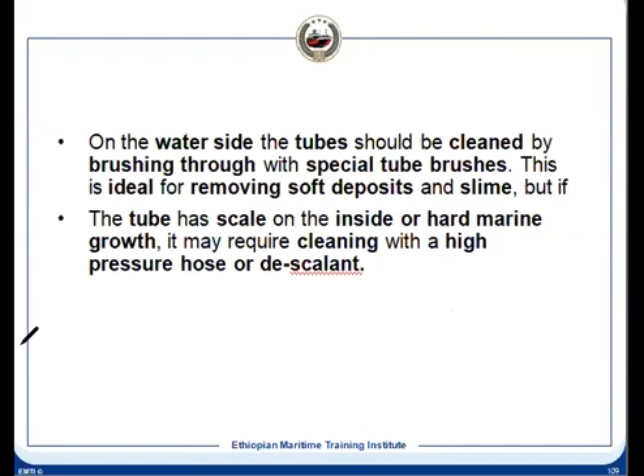Also, if it is seawater cooled, there will be a zinc anode, the sacrificial anode. We must check its condition; if it has been eaten away, consumed, we need to change it. Also, hard marine growth can be removed with a high pressure hose with a descaling chemical, or with the high pressure water alone.